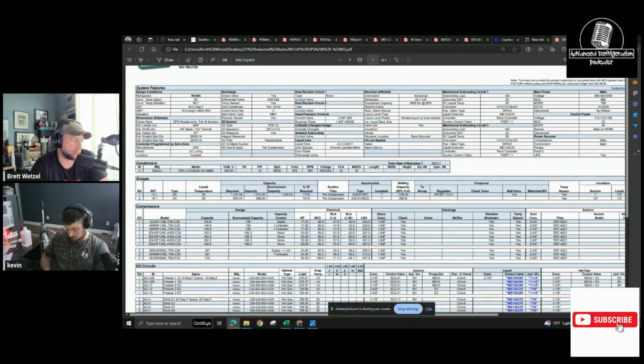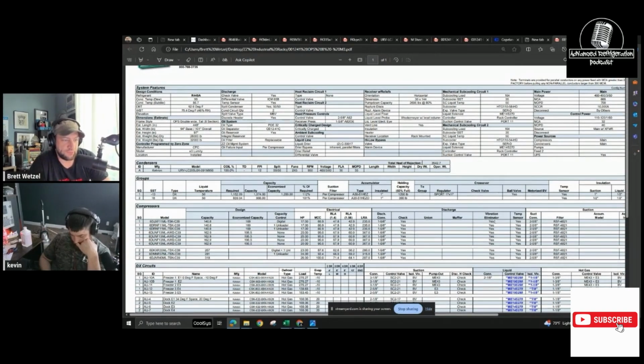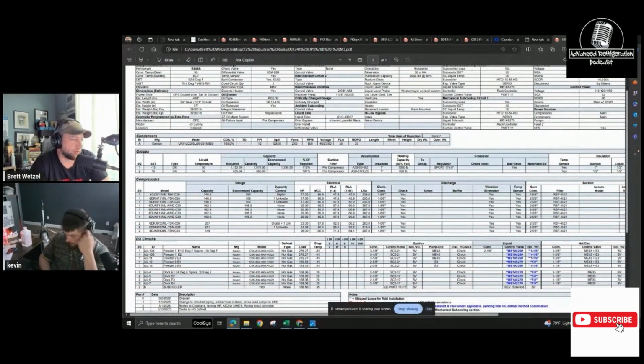We have a plus 13 suction and we have a plus 18 suction. First and foremost, if you're having problems, make sure the rack is in fact running right at suction, or if it's running a little bit higher, maybe that's why you got some cases. Also, a lot of times you will see right up here it says subcooler SST 35 degrees, subcooler liquid temperature 50 degrees. So, knowing if the rack is operating exactly the way it was designed, because 90% of the time, if you get it back to the engineering spec, it should work.